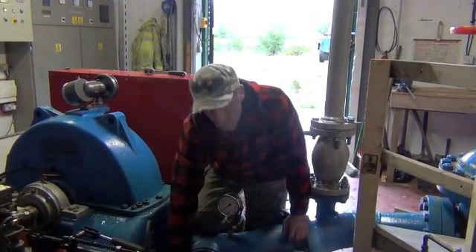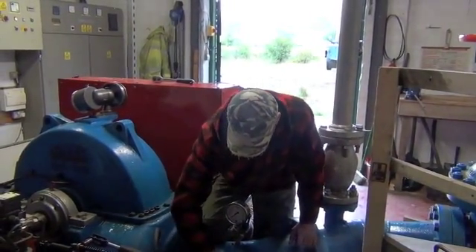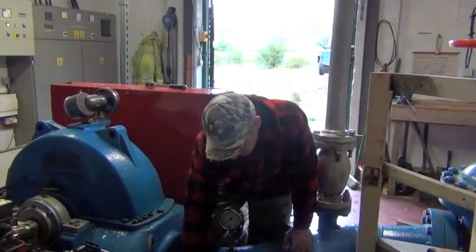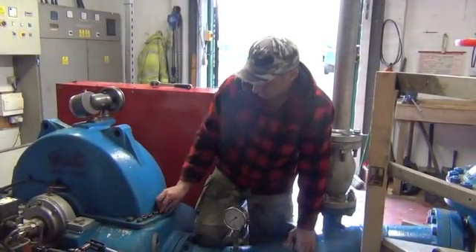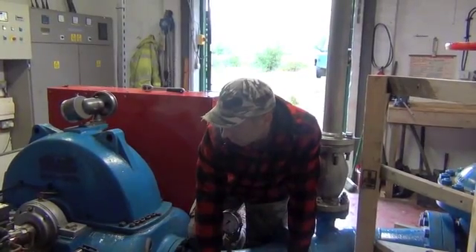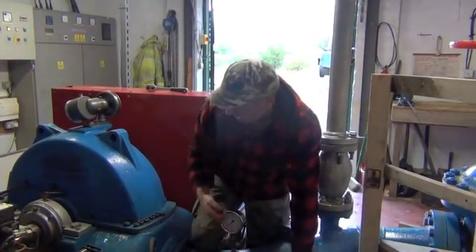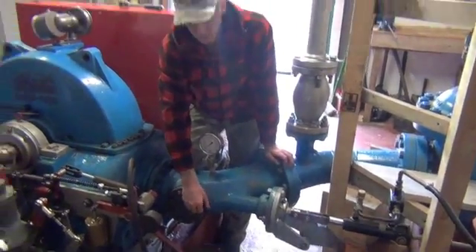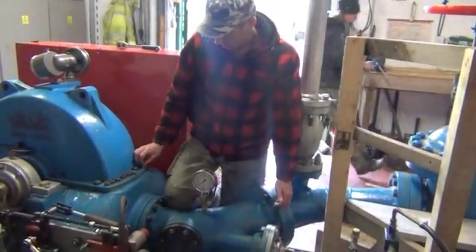We just have a standby diesel generator running at the moment while we've got this shut down to carry out the maintenance. And this is the original turbine? It is, yep. It's a Gilkes Pelton wheel and mechanical Woodward governor, which basically controls the speed of the turbine to keep a constant 50 hertz frequency. And there's an economizer which operates the spear valve here, which controls the flow of water to the turbine, so it's only using the amount of water that it actually needs for the demand on the system at the time.